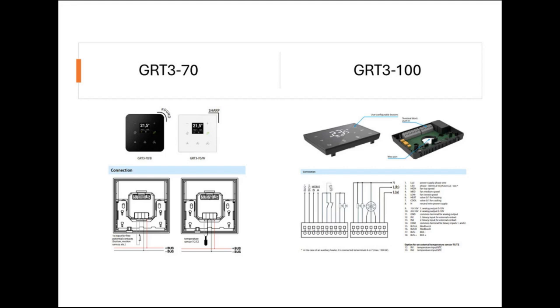And then you can also see another segment with valves, heating or cooling valve, which is analog type. And then you can use inputs like digital inputs or temperature inputs. And then you can see 2 Modbus terminals where it communicates to other systems using Modbus. It acts as a Modbus master. We also have an option to set it as a Modbus slave. So it will control and communicate with the third-party HVAC system using Modbus protocol.